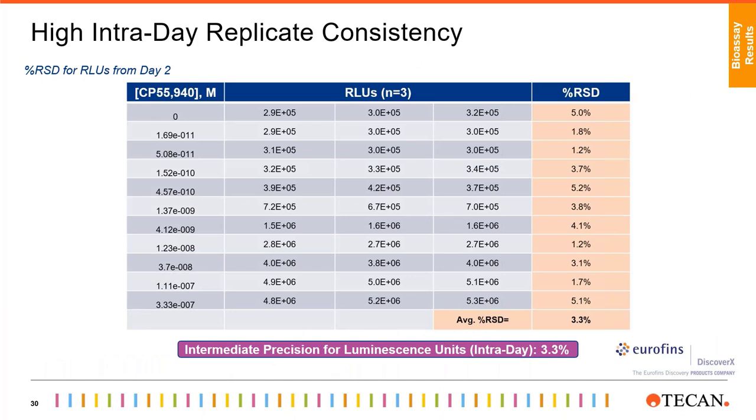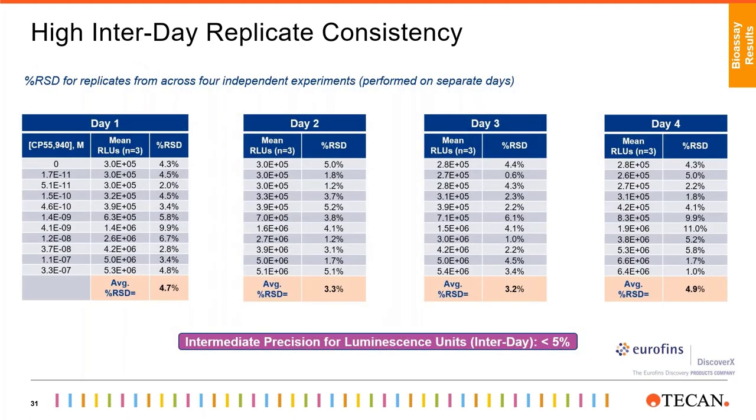Similarly, we looked into intraday replicate consistency. We analyzed the raw luminescence data from the experiment performed on day two and calculated the relative standard deviation. As shown, the replicates for each data point are extremely tight and the average RSD is 3.3%, which demonstrates high intraday replicate consistency. We then compared the interday replicate consistency and summarized the CV obtained for each of the four independent experiments — for each day the average CV is less than 5%, illustrating that the Fluent system provided low day-to-day variability for this assay.